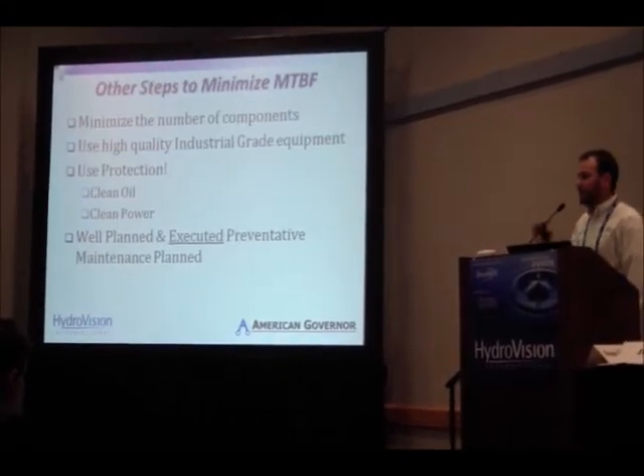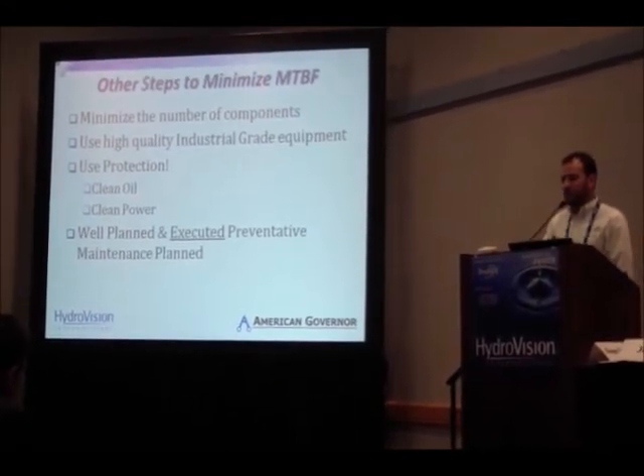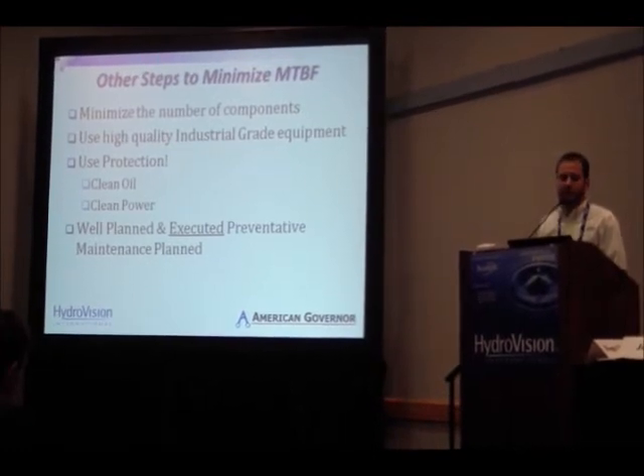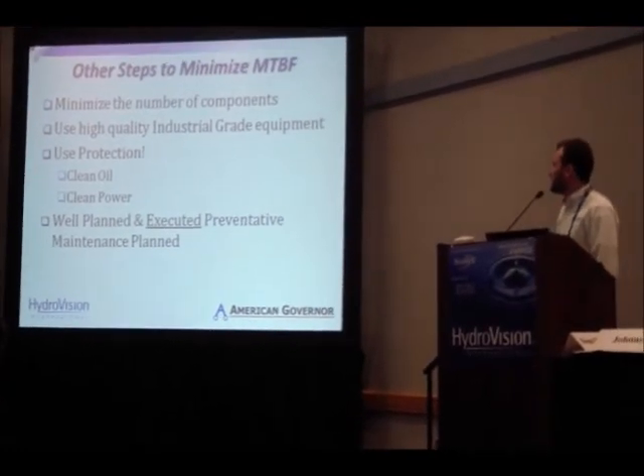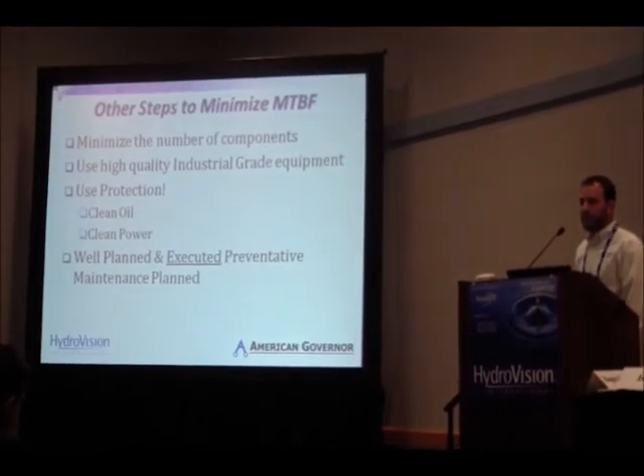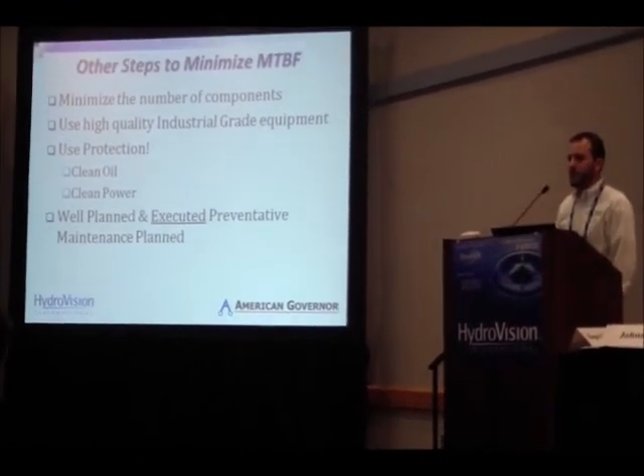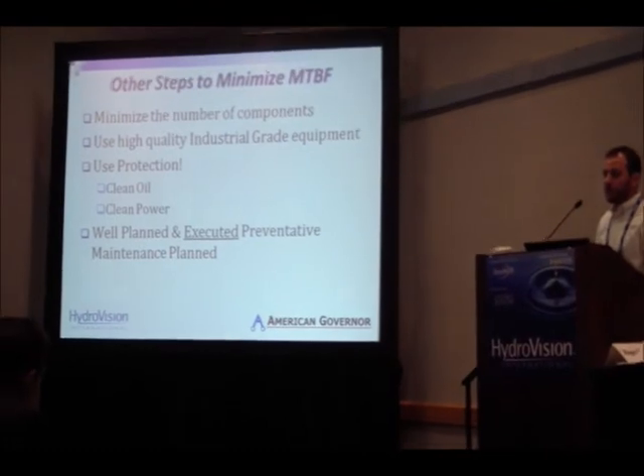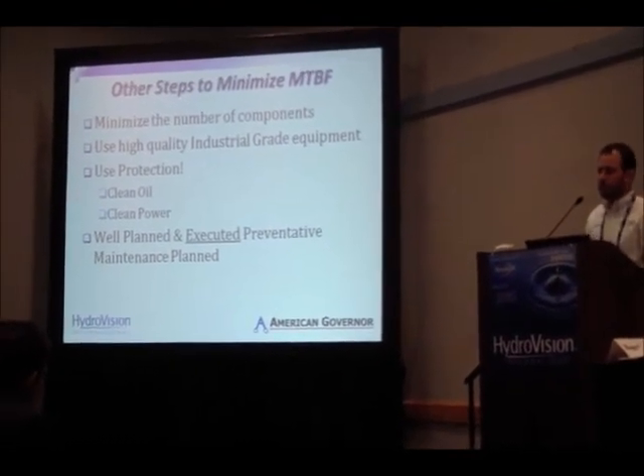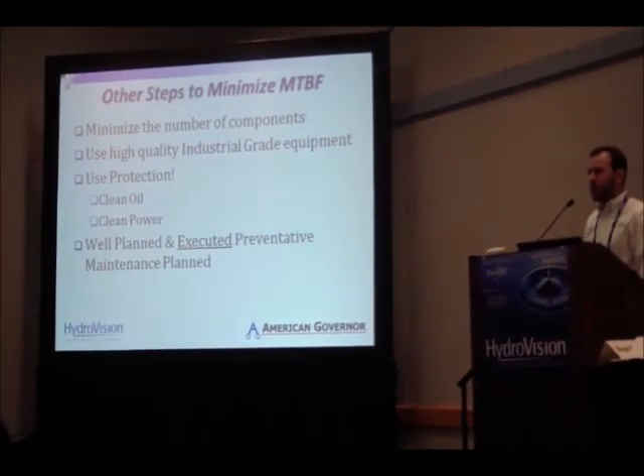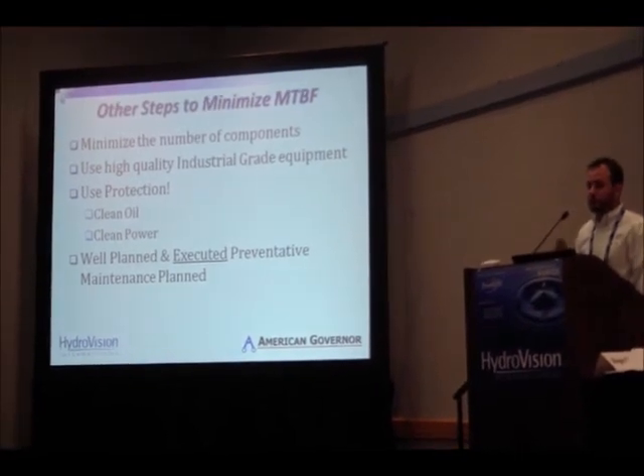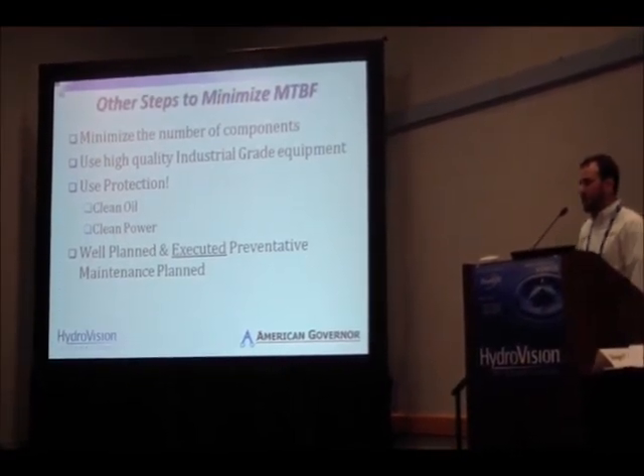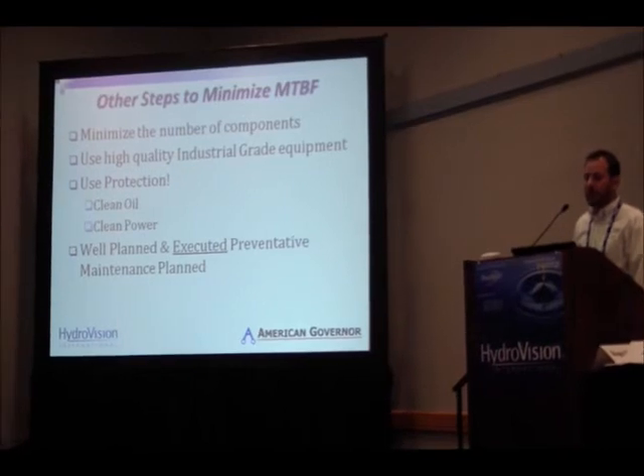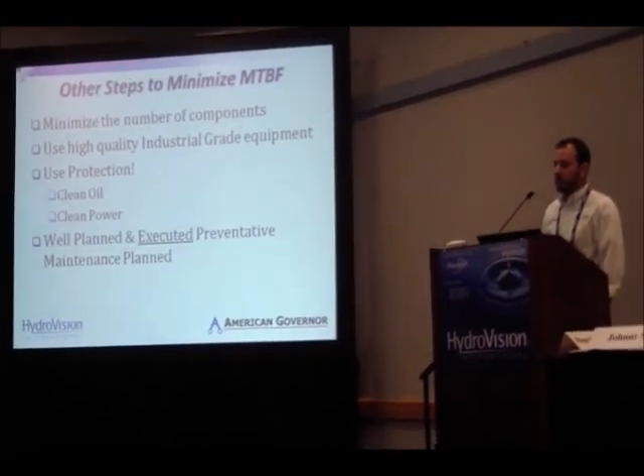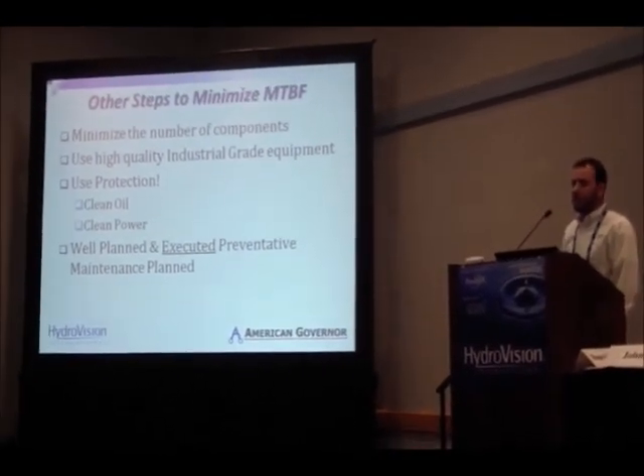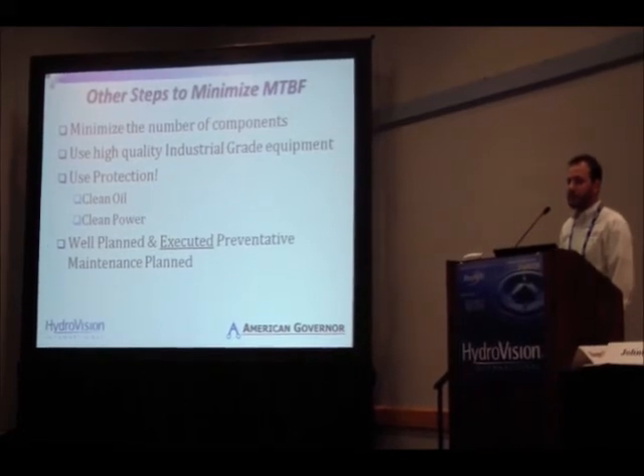Now, on top of the decision making of what level of redundancy, there are other steps you can take to minimize your mean time between failures. One thing you saw as a trend is as we increase equipment, you'll have more equipment failing. So minimize the number of components across the board during your design. Use high quality industrial grade equipment. Use protection, clean oil, clean power, filter your oil. And then a well-maintained, well-executed preventative maintenance plan will minimize the failures that can take your system out.